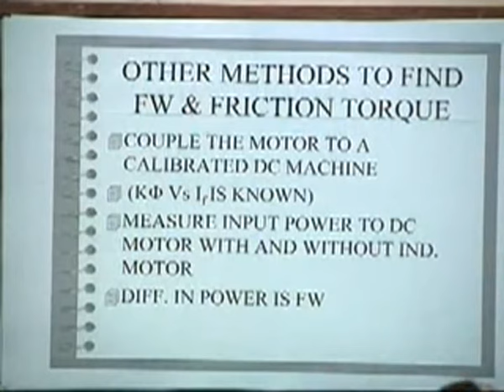Whenever you measure the total power with and without coupling, what will be the difference? The difference arises because your induction machine is not excited, so it doesn't have any core loss at all, or no loss. So the difference will give you the friction windage.